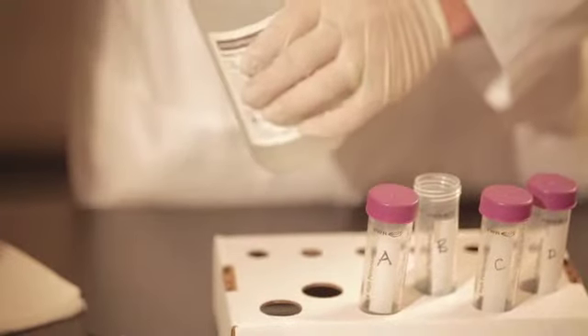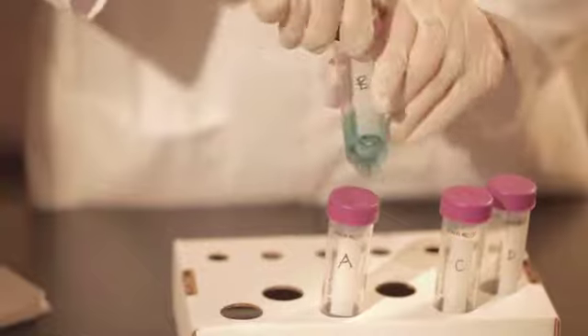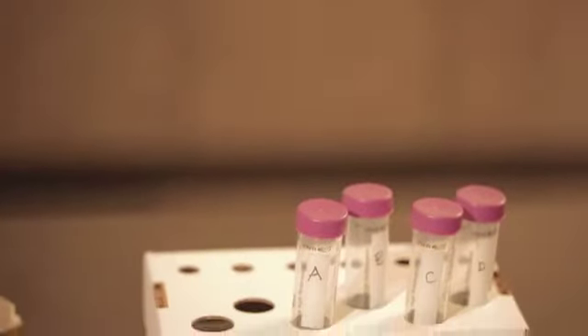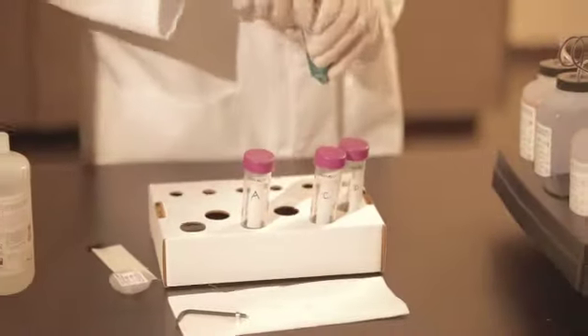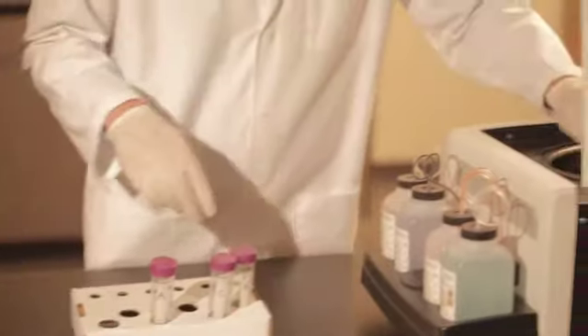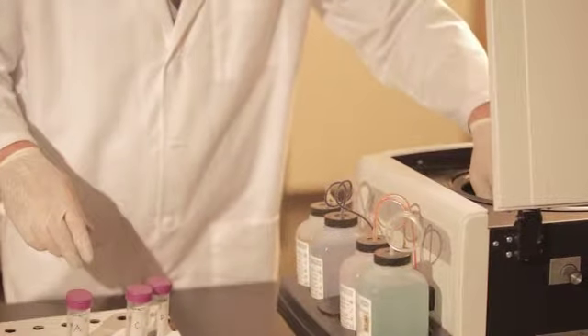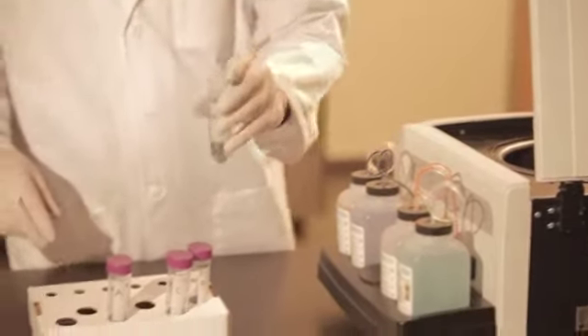Let the nozzles soak for 5 to 10 minutes at a minimum. If possible, let them soak overnight. Be sure to label each tube so that the nozzles are returned to their original location. After soaking, dump nozzle cleaning solution down the drain of the stainer. Place the parts of the nozzle on a paper towel.